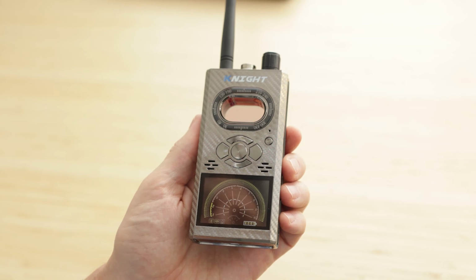So for radio frequency detection, once you turn the device on, it's automatically in radio frequency detection mode, and you can simply turn the device all the way up, and it's alarming. It's probably picking up your Wi-Fi or your neighbor's Wi-Fi once you do that. And you can little by little turn it down until you can see a sensitive and flickering radio frequency dial there, but to the point where it's not quite alarming. At this point, you're ready for radio frequency detection, and we can go searching for any kind of signals you might want to locate.